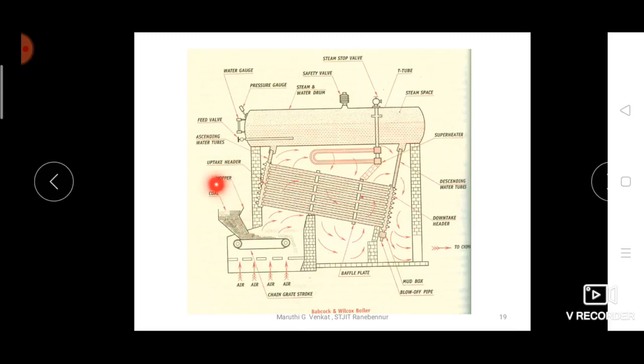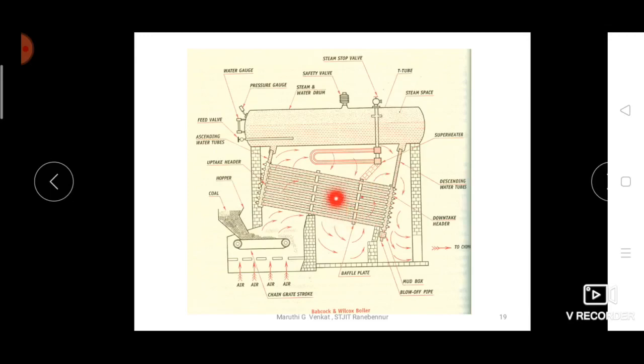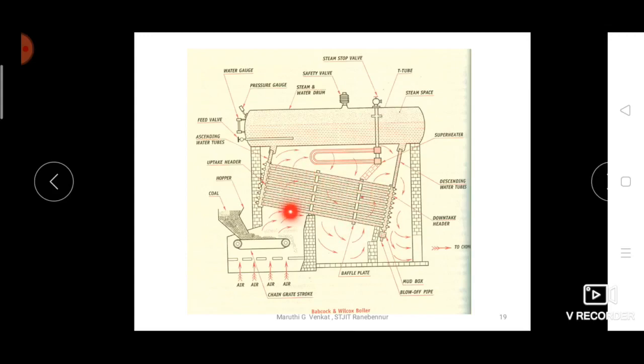In terms of working: using the hopper, coal is placed on the grate. Atmospheric air enables the combustion process, releasing hot flue gases. The baffle plates guide these hot flue gases over the inclined water tubes. Water inside the inclined tubes absorbs heat from the hot flue gases and is converted into steam, which is then collected at the top surface of the water using the uptake header.